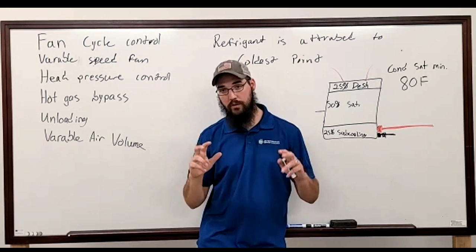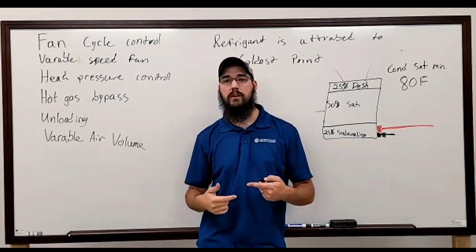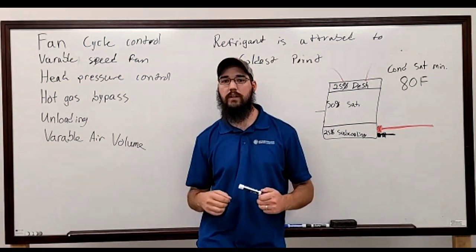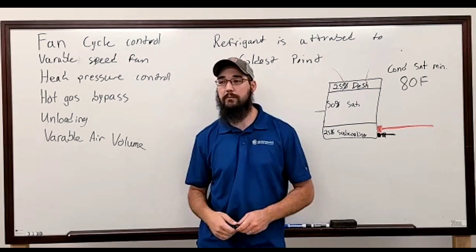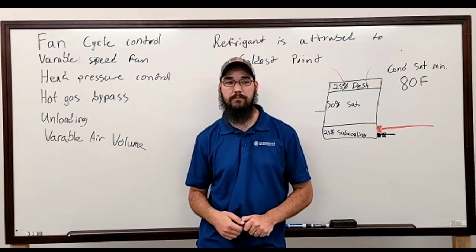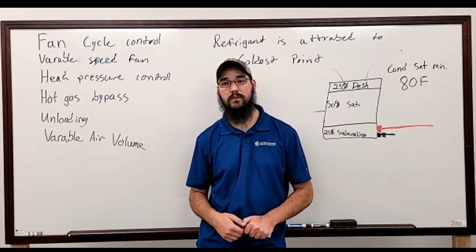And when it comes to overclocking, this is something you're going to want to be preparing yourself for now. The day and age where everything is a flat line 60 hertz is quickly evolving. We have air handlers now that come from the factory designed at 88 hertz on the motors. I saw that compressor ramp up to 200. It just blew my mind because I'm used to seeing that at max, you go like over three times.